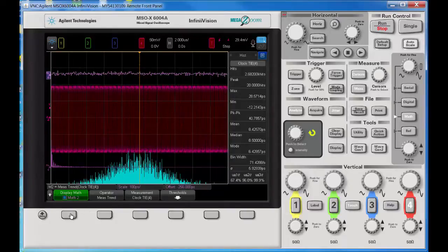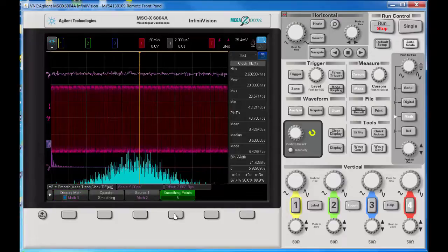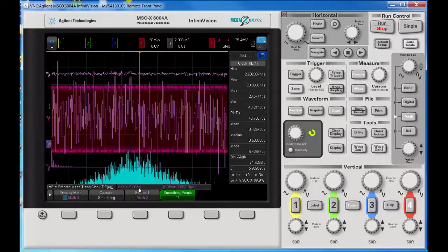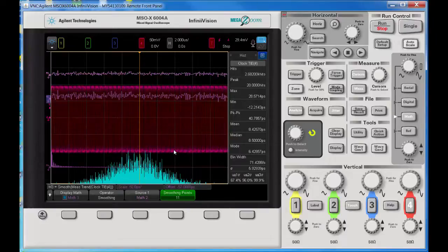Now let's turn on the TIE that's been smoothed. I'll select the smoothing points to be 11, and I'm going to adjust the vertical scale to 50 picoseconds and the offset to negative 57 picoseconds.